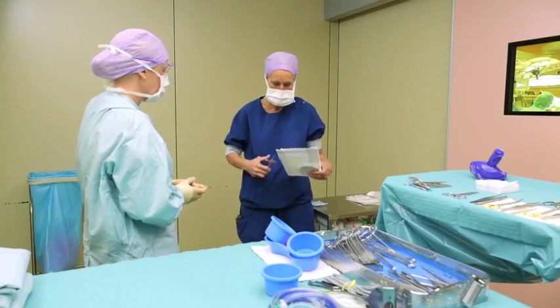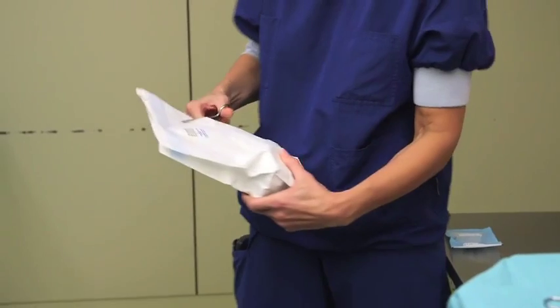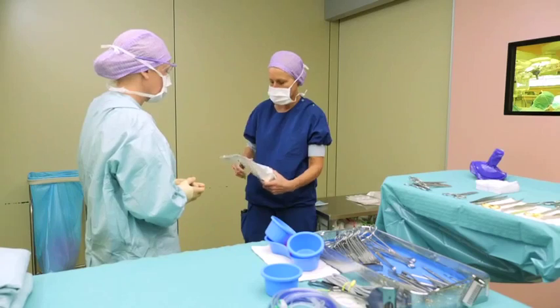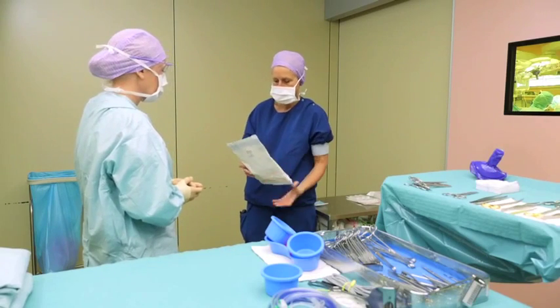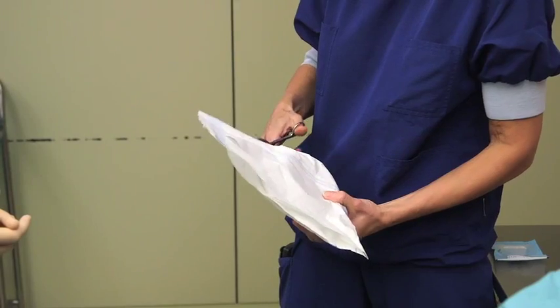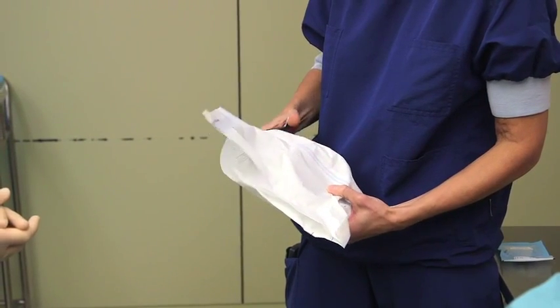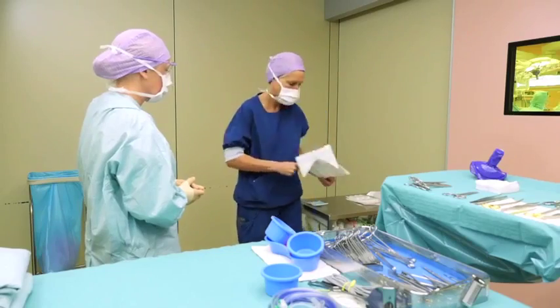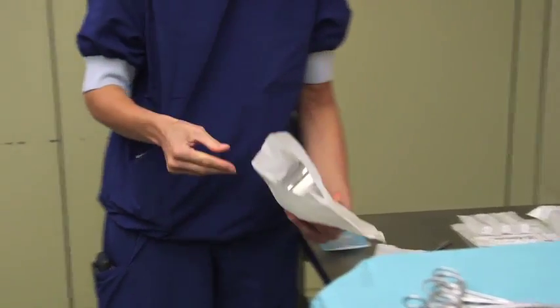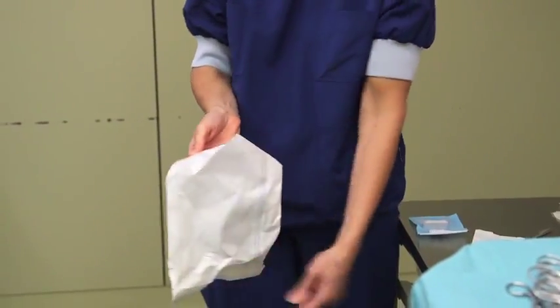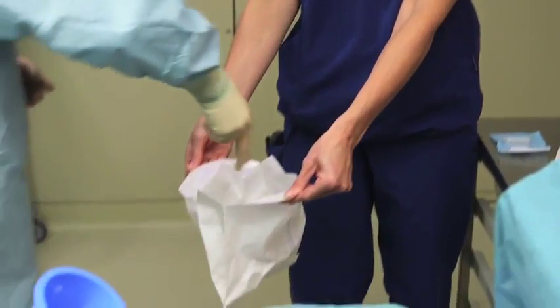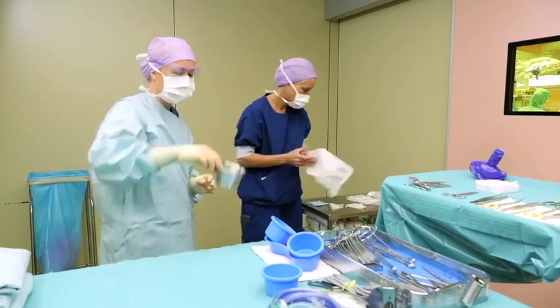To enable aseptic opening of a heat-sealed paper bag, it's recommended that scissors are used and a cut made from the side of the bag up towards the bottom middle of the heat-sealed area. This should then be repeated on the opposite side, leaving a pointed center. Hold each side of the pointed corner and roll your hands down, exposing the instrument that needs to be removed.